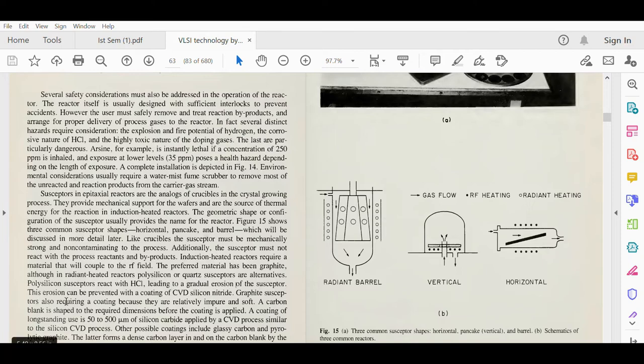Graphite susceptors also require a coating because they are relatively impure and soft. A carbon blank is shaped to the required dimensions before the coating is applied. A coating of long-standing use is 50 to 500 micrometers of silicon carbide applied in the CVD process similar to the silicon CVD process.